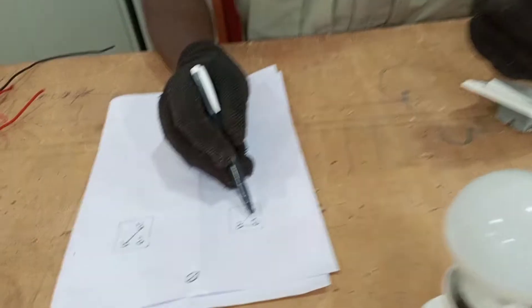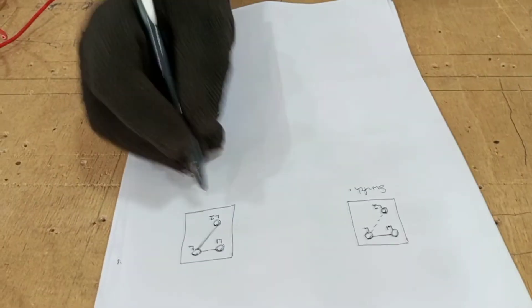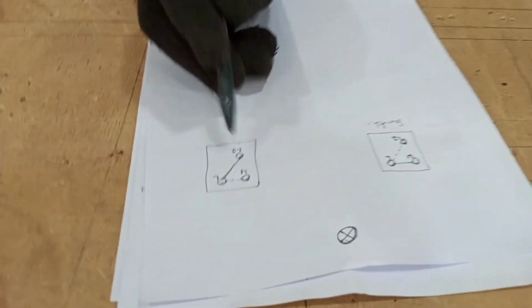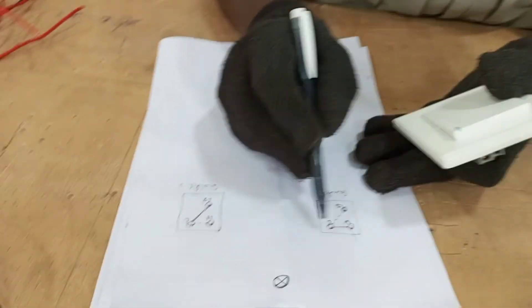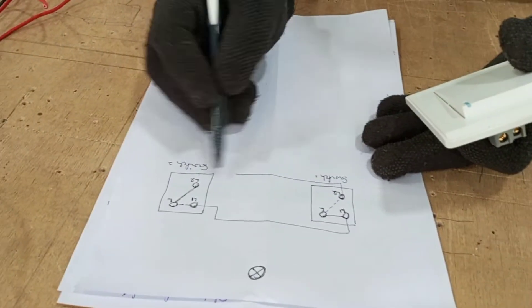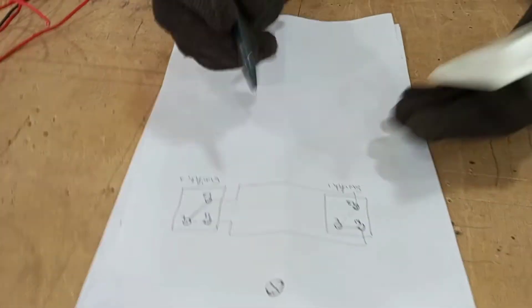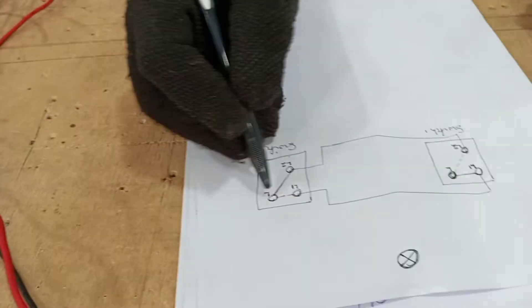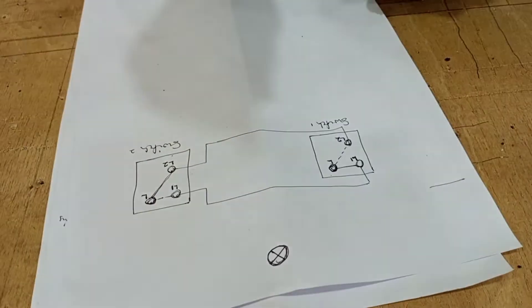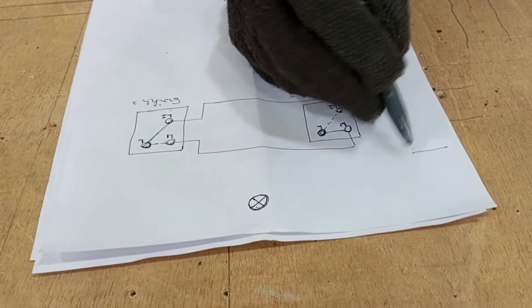For two-way switching, you will need two two-way switches. L1 and L2 from switch 1 will connect to L1 and L2 at switch 2. So we connect L1 here to L1 there, and then we connect L2 here to L2 there. That will leave the L terminal on each switch — one of these L terminals will be connected to the feed, which is usually taken from a fuse or a circuit breaker.